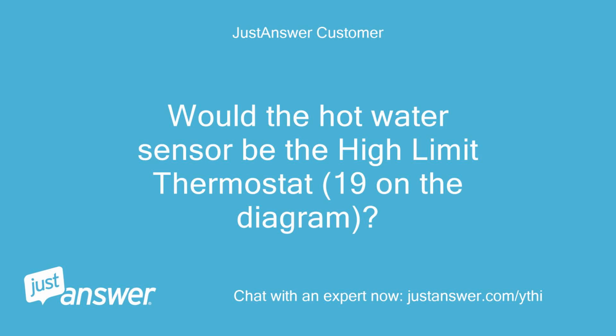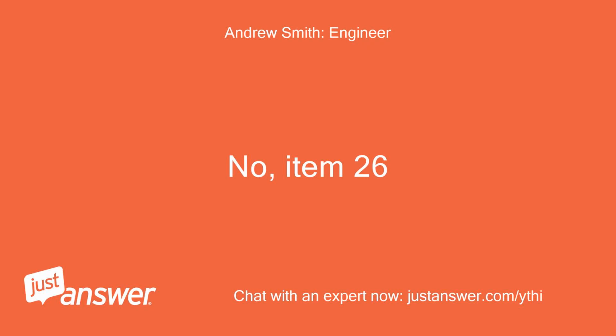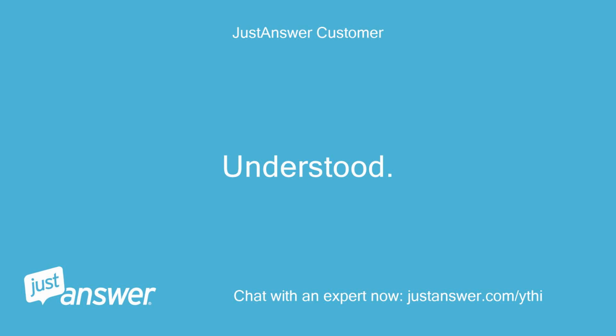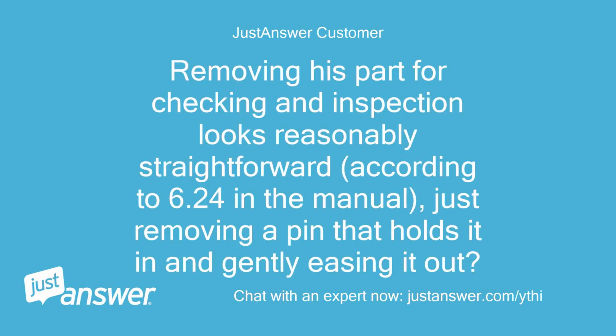Would the hot water sensor be the high limit thermostat, 19 on the diagram? No, item 26. Understood. Removing this part for checking and inspection looks reasonably straightforward, according to 6.24 in the manual, just removing a pin that holds it in and gently easing it out.